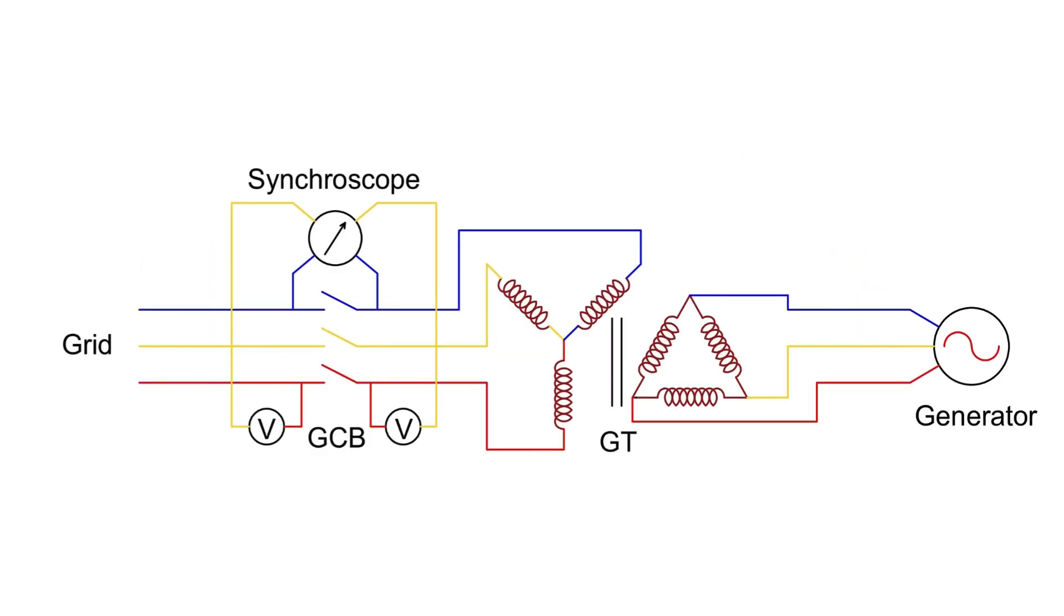For voltage magnitude, two voltmeters are used, one for the grid and one for the incoming generator. To monitor frequency and phase angle, we have the synchroscope. When the frequency and phase angle are almost the same, the synchroscope signals that you can close the GCB.